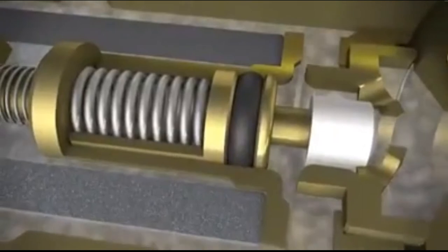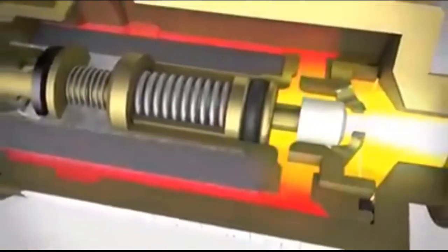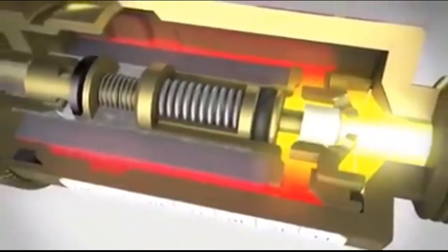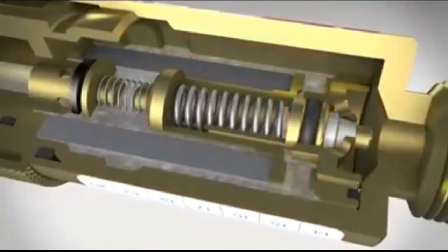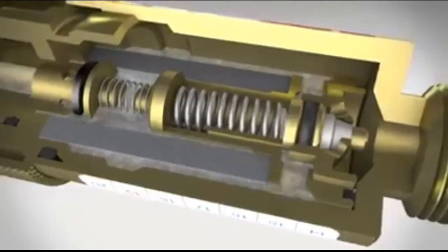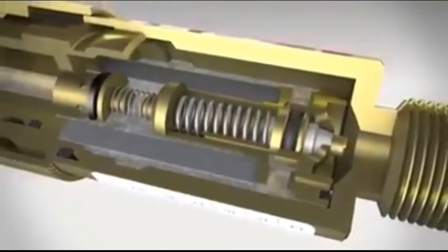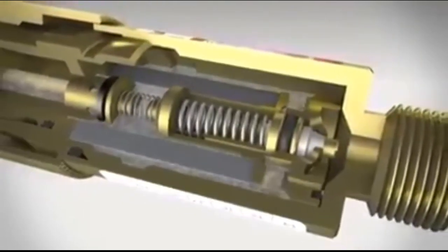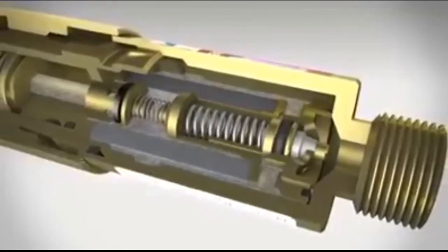The temperature-sensitive cut-off valve is the third important protection element. The integrated plastic body melts and the spring-loaded valve triggers before the device can heat dangerously. This automatic interruption of the gas supply prevents a critical ignition temperature from forming at the gas inlet. A dangerous back-burning is stopped at source and remains without damage.